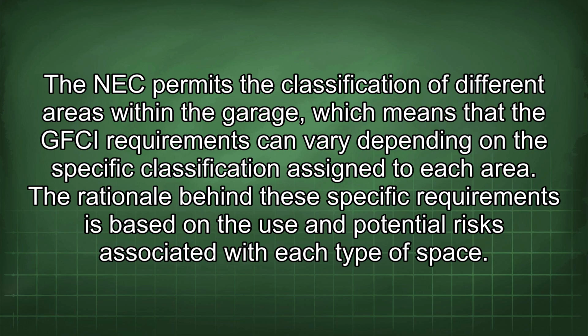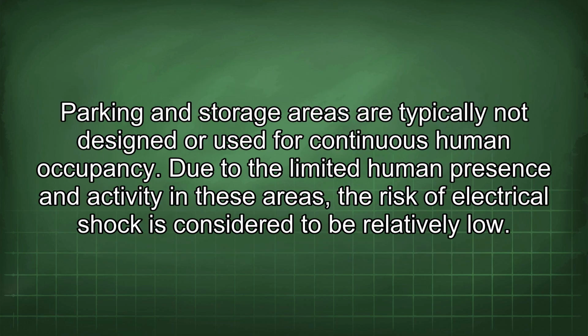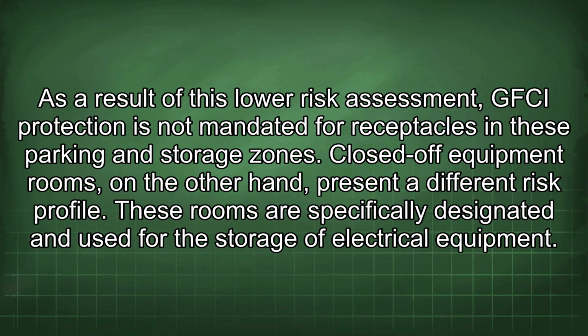The NEC permits the classification of different areas within the garage, which means that the GFCI requirements can vary depending on the specific classification assigned to each area. The rationale behind these specific requirements is based on the use and potential risks associated with each type of space. Parking and storage areas are typically not designed or used for continuous human occupancy. Due to the limited human presence and activity in these areas, the risk of electrical shock is considered to be relatively low.